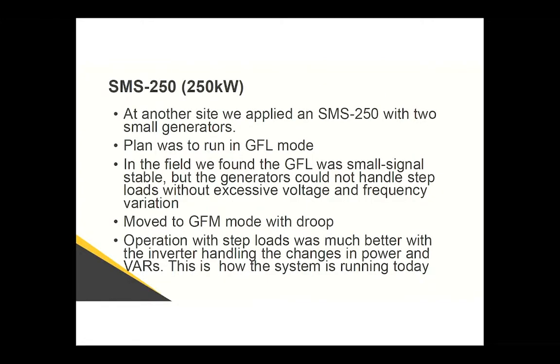We had another site where we had a small 250 kilowatt inverter coupled with a couple small generators, sort of an island system. The inverter was there to help support the generators, but it was running in a grid following mode. And what we found was in that mode, while everything was stable, the generators couldn't keep up with the changes in load. And so we'd see frequency and voltage variations that were beyond what they wanted with the steps that they were putting on it. So we switched over to a grid forming mode and everything stabilized out.